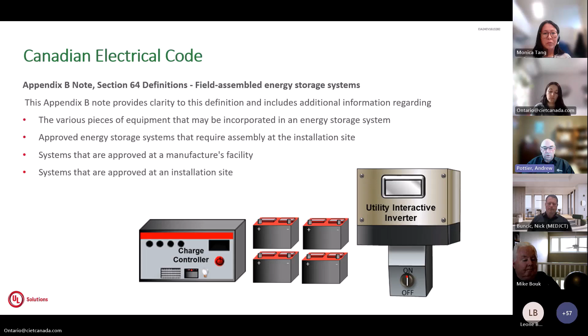The installer of the energy storage system is required to follow the manufacturer's installation instructions when reassembling it. Alternatively, an energy storage system could be built on site by an installer using batteries, inverters, charge controllers, and other associated equipment that hasn't yet received an overall approval. If that is the case, it is still required to be approved, probably through a field evaluation based on an SPE 1000 model code, and it would also be inspected by the local inspection authorities.